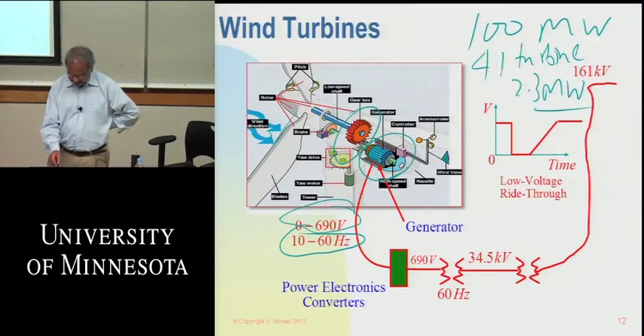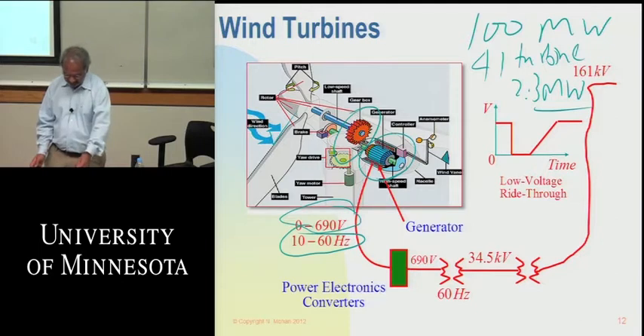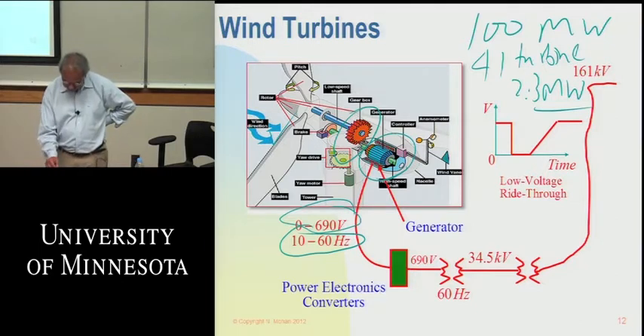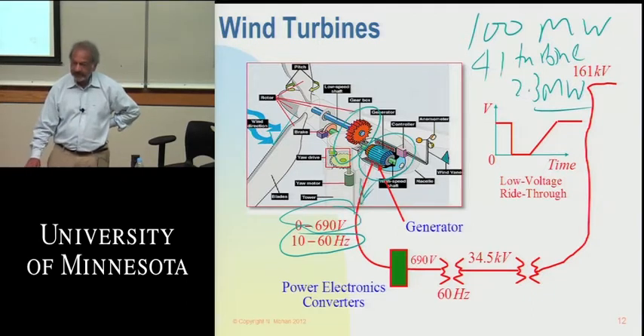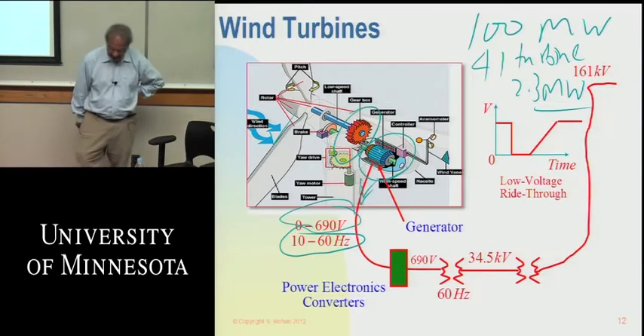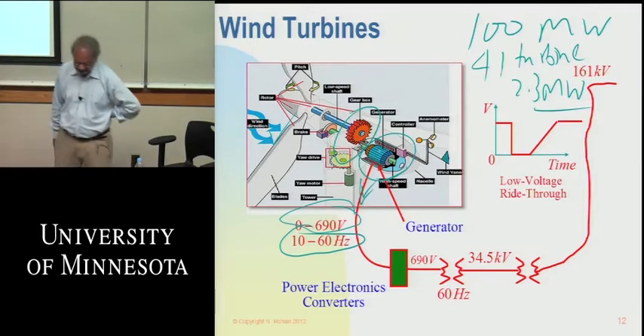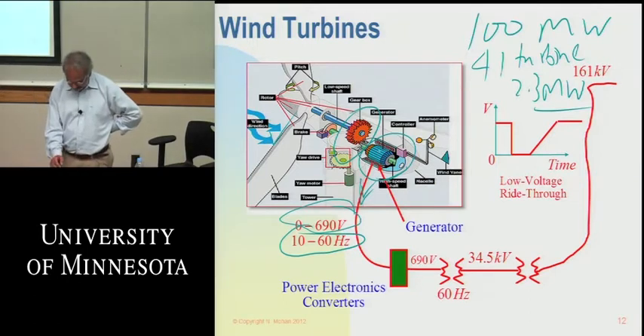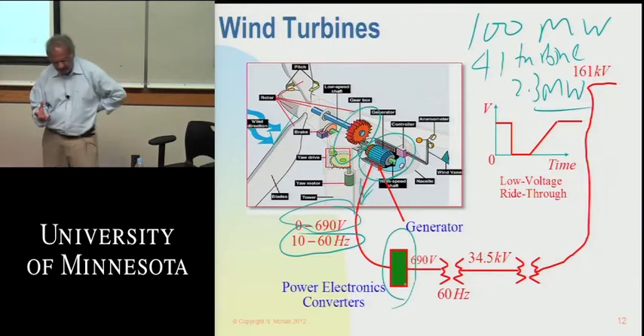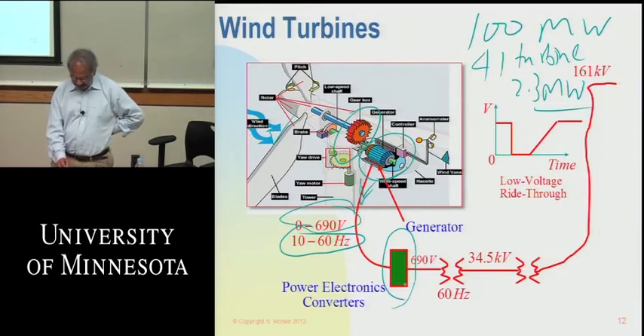So generating this power of 2.3 megawatts at rated condition and transferring it at this low voltage of 690 volts, a lot of current has to come down through this cable, as much as 2,000 or 2,500 amps under rated conditions. At the base of each tower there's a power electronics converter, whose role is to take this variable amplitude, variable frequency voltage and convert it to a constant amplitude, constant frequency voltage, 60 hertz.